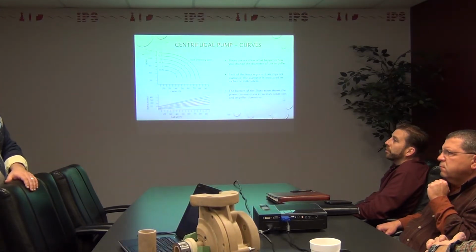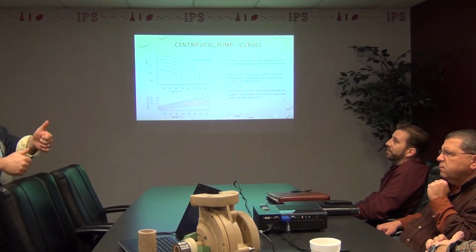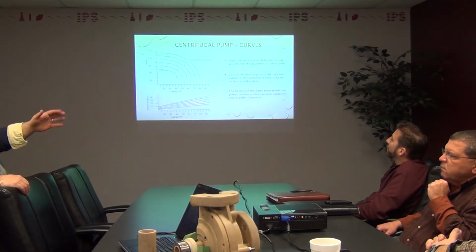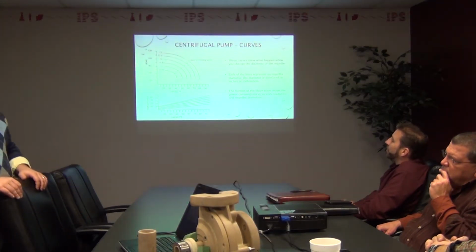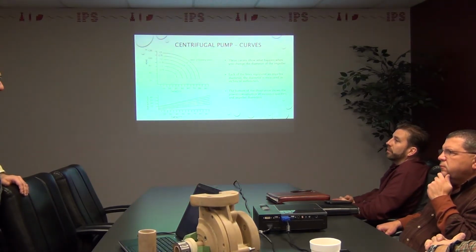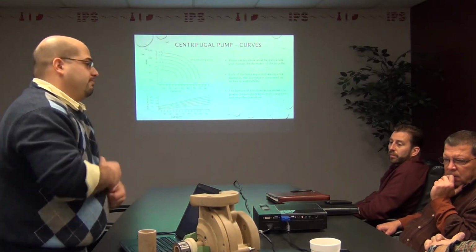Another engineer looks at it, hey, let's tag on another 15%. Rule of thumb, we don't want to be short. Tag on 50. So you put the pumps in, and next thing you know, they don't have enough back pressure. So I sell a lot of orifice plates to compensate for that early in projects, and that's usually the number one issue. It doesn't make sense that you put extra load on the pump and it takes less horsepower.